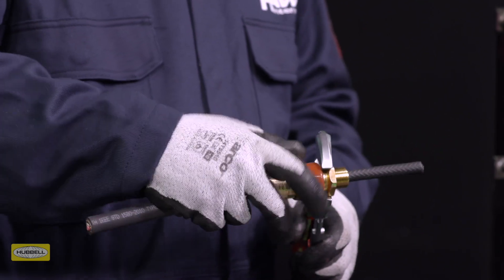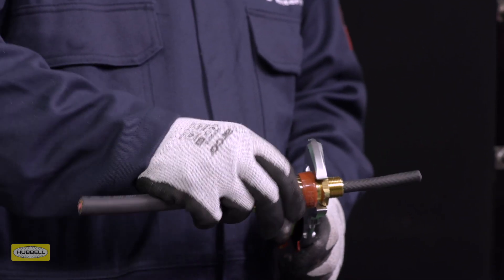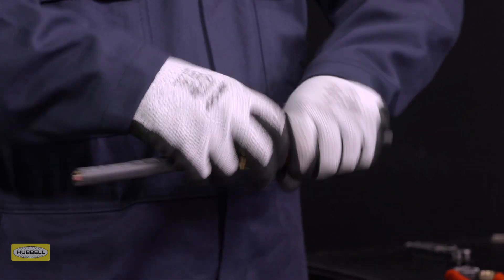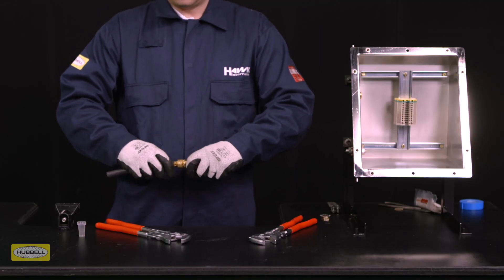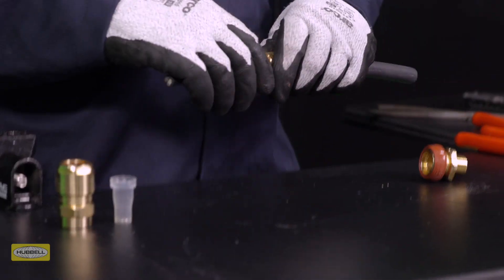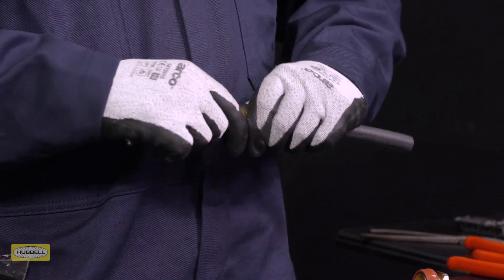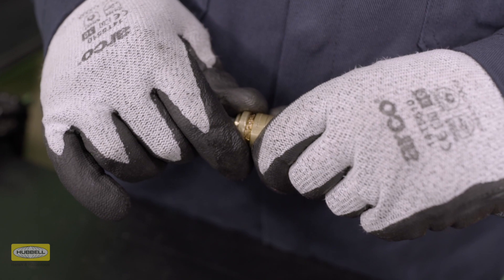Unscrew the middle nut. The armor clamping ring should now be locked in place. Visually inspect that the armor or braid has been successfully clamped between the spigot and the armor clamp ring. If it isn't satisfactory, repeat the previous step.